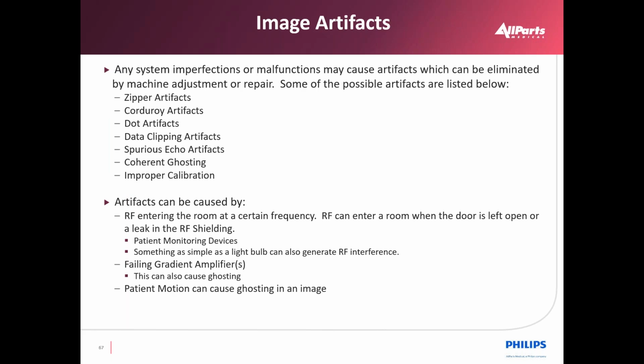Any system imperfections or malfunctions may cause artifacts. These can be eliminated by machine adjustment or repair. Some of the possible artifacts for malfunctions are listed below. Zipper, corduroy, and ghosting are the most prevalent hardware artifacts. Artifacts can also be caused by RF frequencies leaking into the scan room or accidentally brought in with non-conforming monitoring equipment or even faulty light bulbs. Ghosting can also be caused by patient motion while scanning.